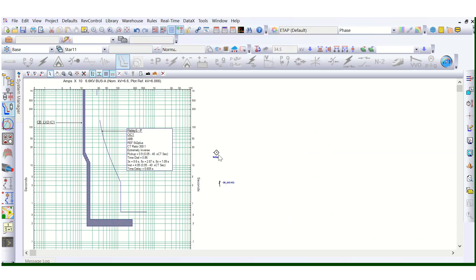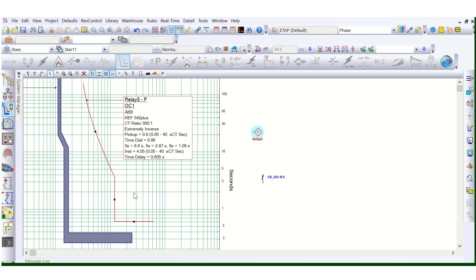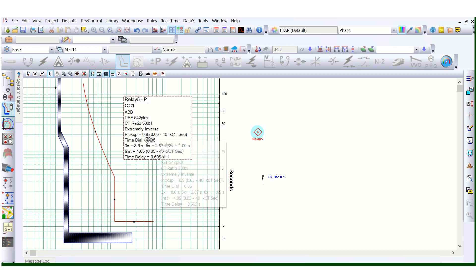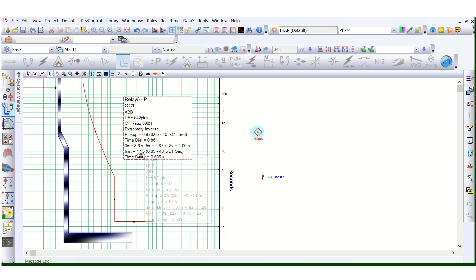Here in this IDMT curve, the settings are: CT ratio 300/1, ABB REF 542plus relay, extremely inverse curve selected, pickup is 0.9, and the time dial of this IDMT 51 is 0.86. The instantaneous setting is 4.05, and the time delay is 0.605 seconds. Truly speaking, this is not actually the instantaneous setting — this is not 50.